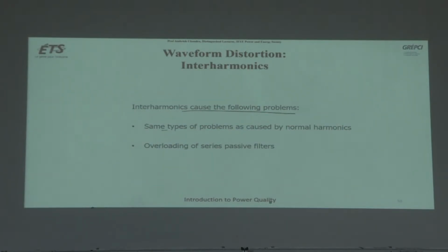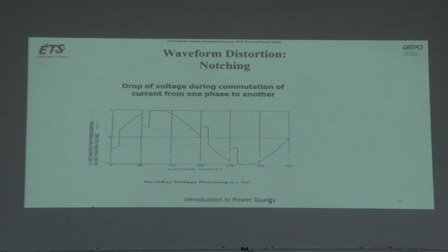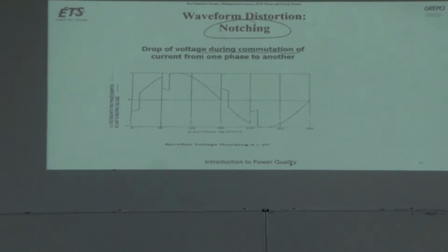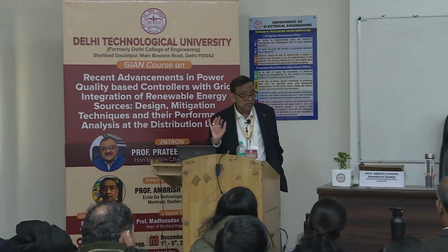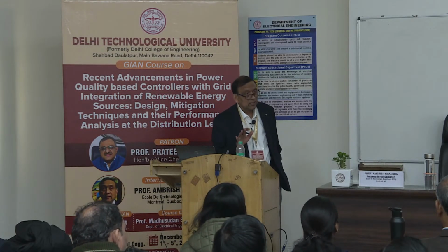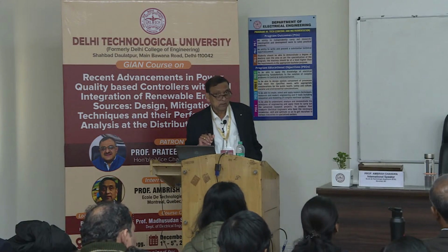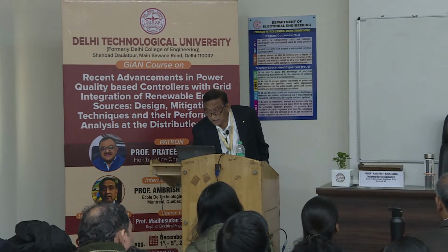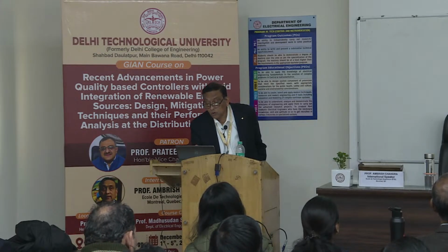Interharmonics cause the same type of problems as caused by normal harmonics. Overloading of series passive filters: because it may not be 5, it will be 5.5 or 4.5, but it will overload your passive filter. Drop of voltage during commutation, notching. Earlier I thought they were no longer talking about notching, this was in 1992, but then I verified that IEEE Standard 519 2014 and even 2022 still keep this, because thyristors are still very much in use for higher power applications. So this is the notching caused by commutation overlap.